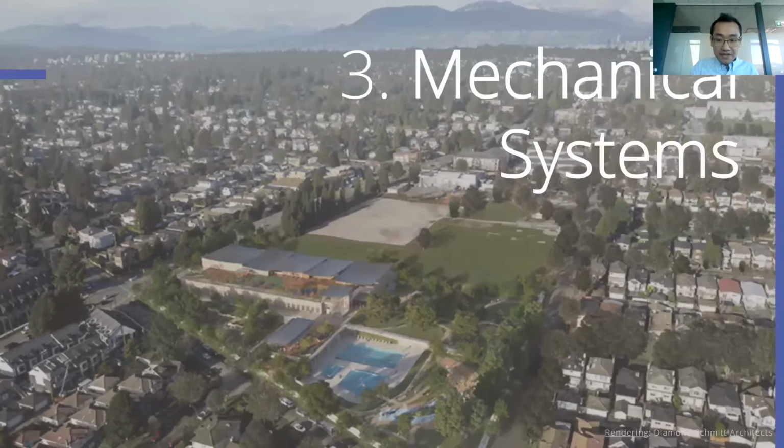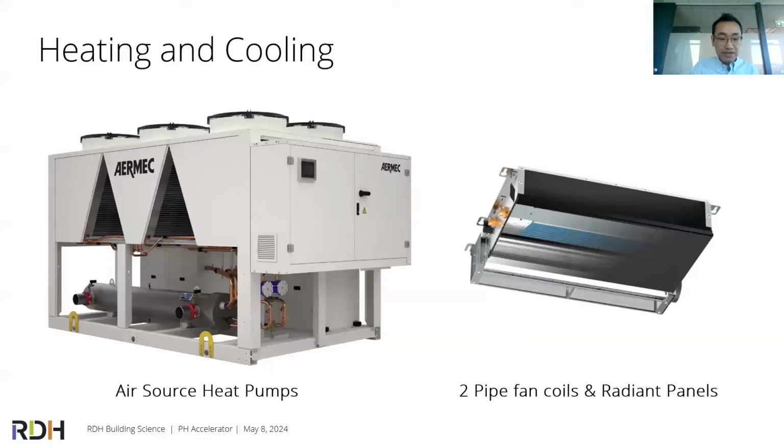In terms of mechanical systems, we're using air source heat pumps for heating and cooling, and hydronic 2-pipe fan coils and radiant panels. Passive House buildings are characterized by super insulated enclosures and exceptional air tightness, which lends itself to a high thermal inertia. So it plays a role in selecting some of these terminal systems.